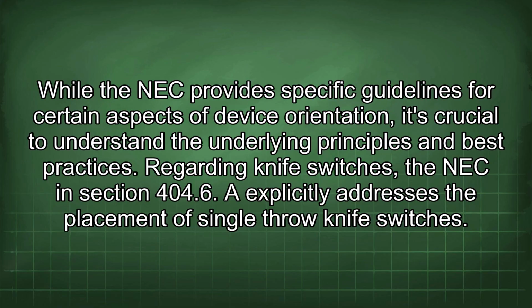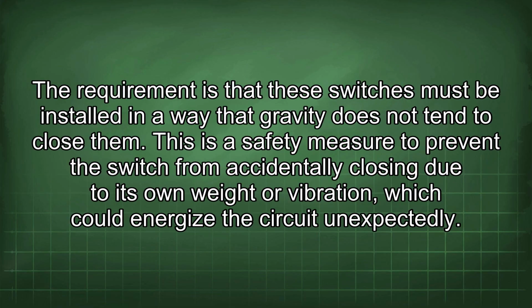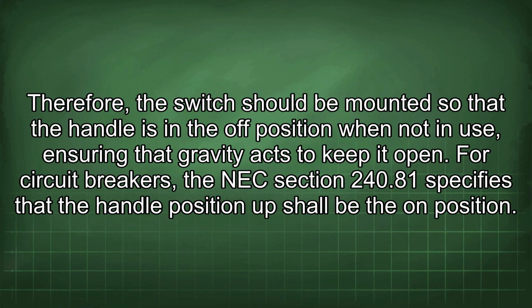Regarding knife switches, the NEC in Section 404.6 explicitly addresses the placement of single-throw knife switches. The requirement is that these switches must be installed in a way that gravity does not tend to close them. This is a safety measure to prevent the switch from accidentally closing due to its own weight or vibration, which could energize the circuit unexpectedly. Therefore, the switch should be mounted so that the handle is in the off position when not in use, ensuring that gravity acts to keep it open.